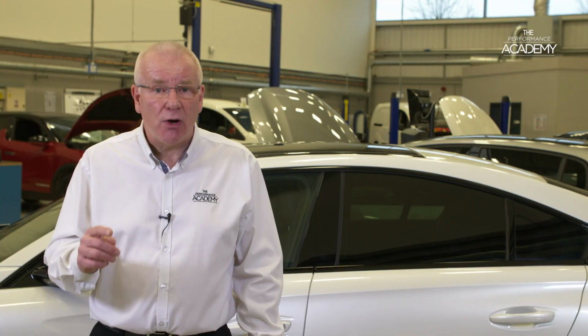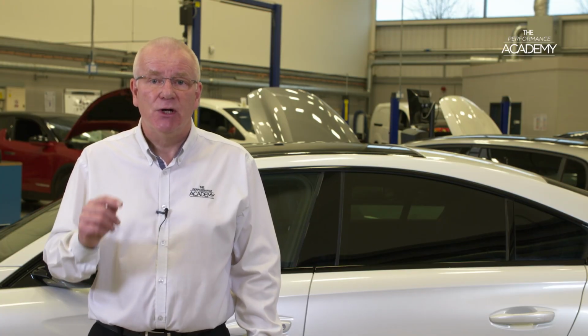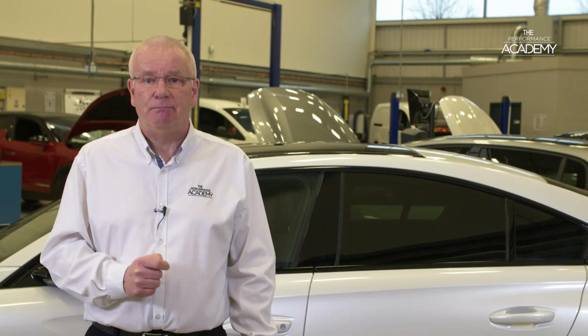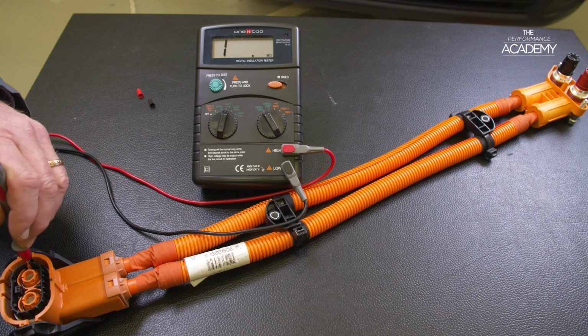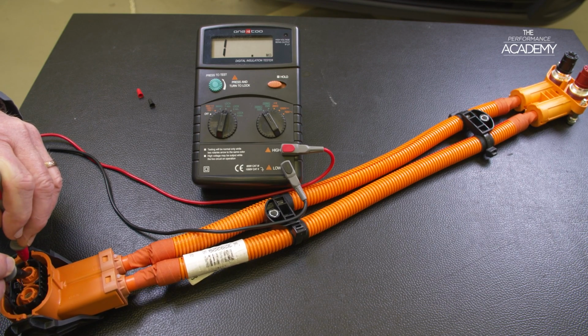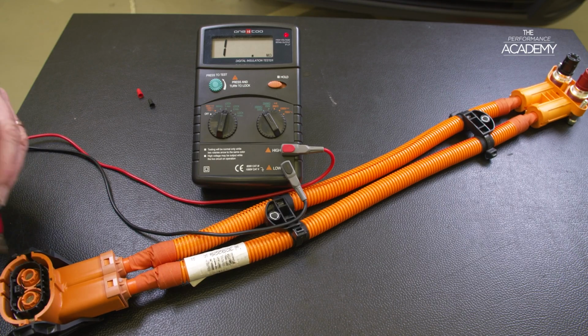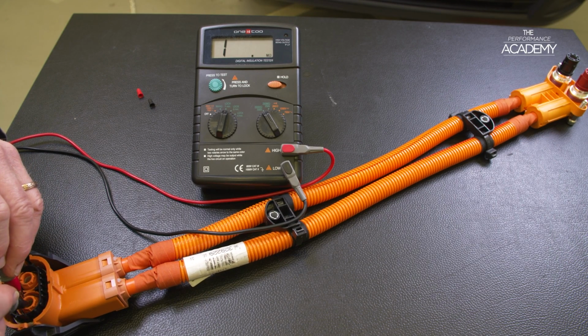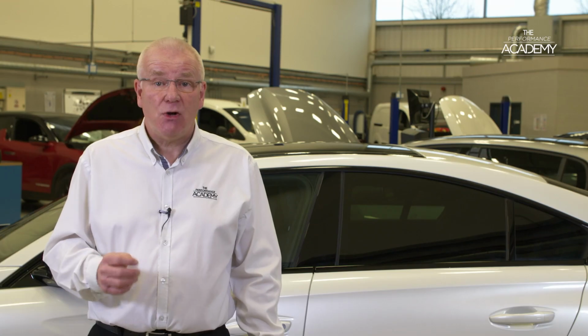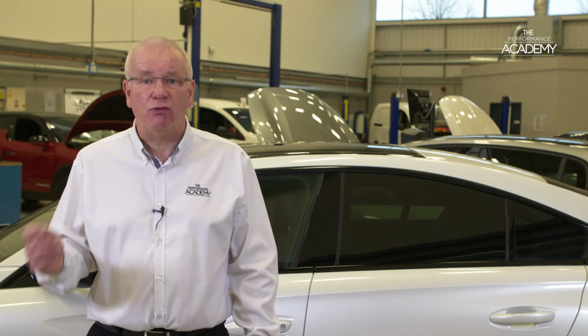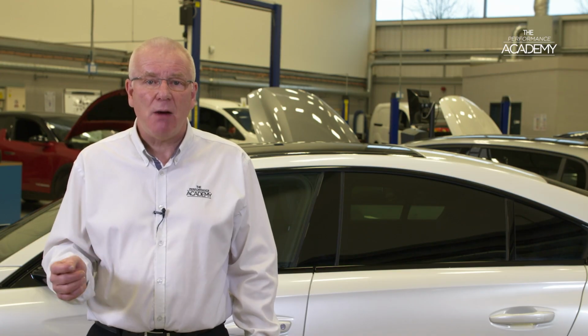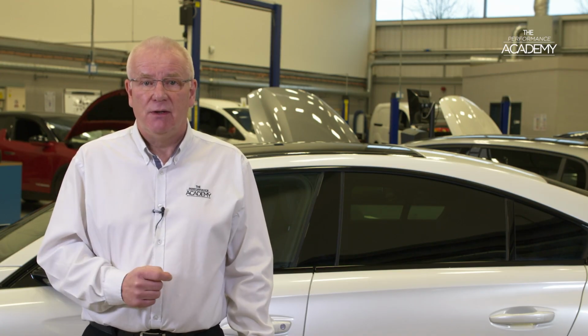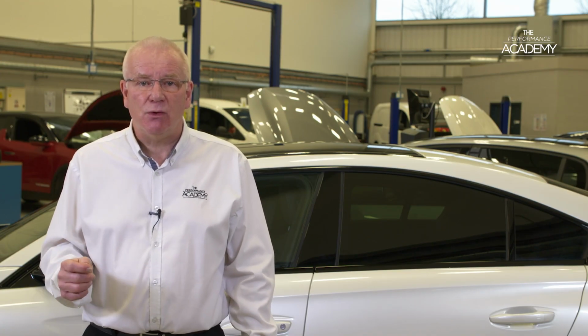Always double check your probe connection points if this happens to ensure you have a good reading. Disconnected high voltage cables tested separately should always give an open circuit reading, or just one, as the screen and the conductors should be perfectly insulated from each other. As long as the value read is equal to or greater than the resistance value published by PSA for the test, the main installation is serviceable and safe.